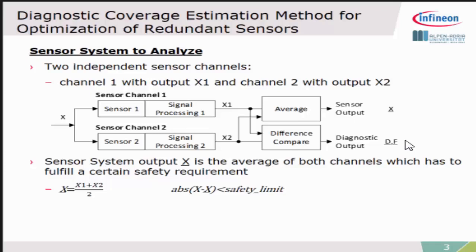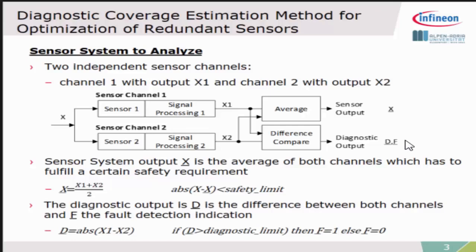We also have a safety requirement from the system which means the deviation from our sensor output compared to the real value should be smaller than a certain safety limit. This was checked by this diagnostic function where we are calculating the difference. If the difference is exceeding a certain diagnostic limit, then we should raise a kind of failure flag so we can diagnose this point.